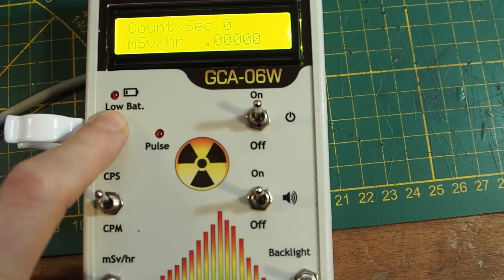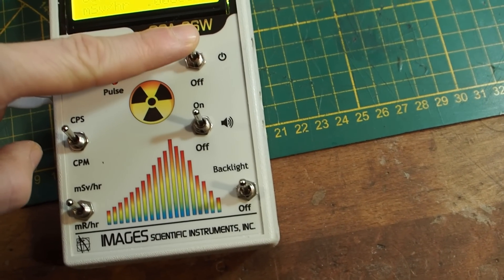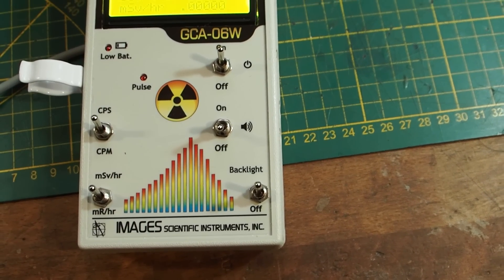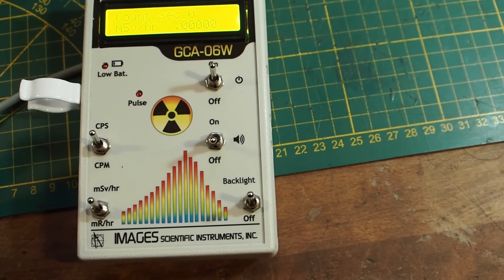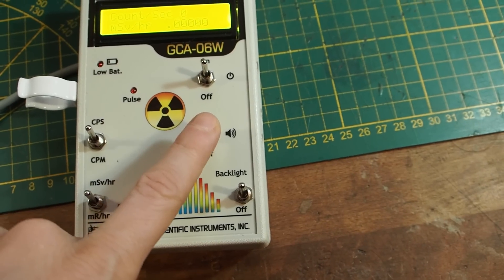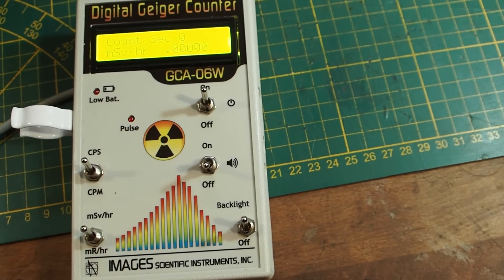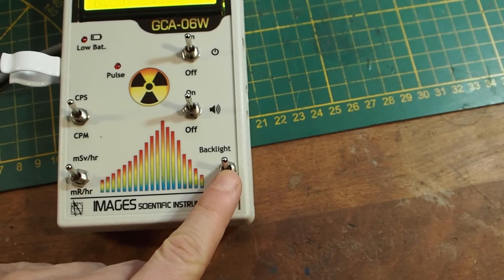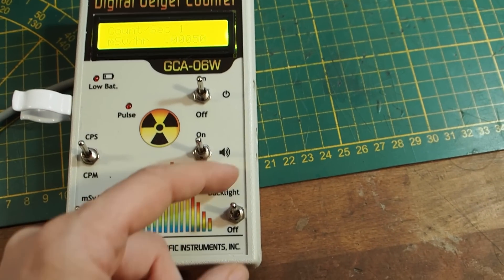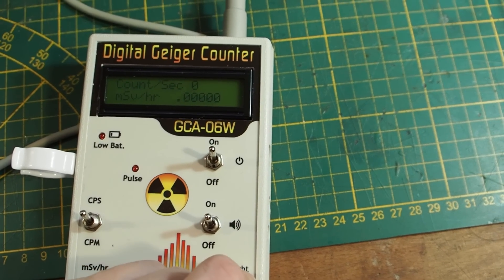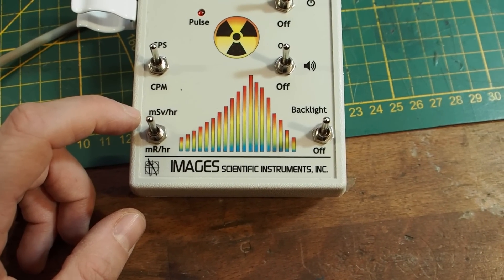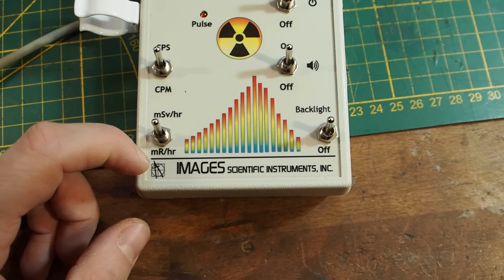Then also here we have an indicator for low battery. This is the power switch. With this switch here you can turn off the sound. So sometimes you don't want to attract any attention and then switching off the sound is a good thing but then you still have the pulse LED. Then here you have another switch which can switch off and on the backlight to save some battery and then here you have a switch which is letting you decide between millisievert and milliroentgen per hour.